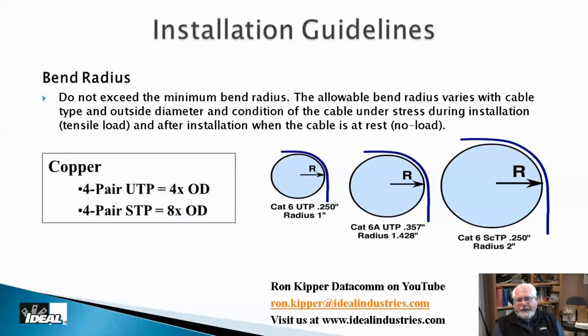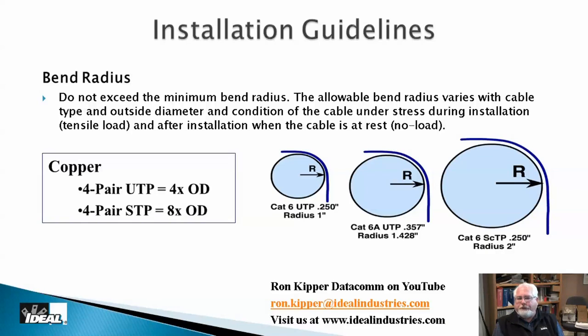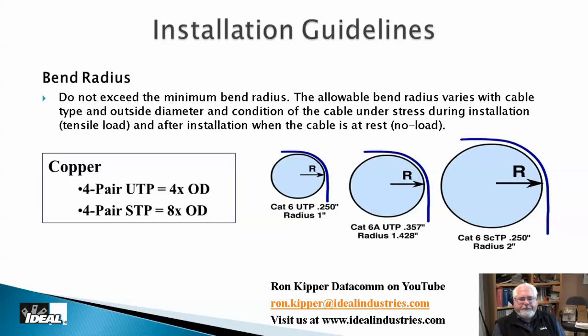Bending radius for UTP cable should be no tighter than four times the cable's outer diameter. Most category cable is roughly a quarter inch in diameter, so the minimum bend radius is one inch — meaning the tightest loop you should form is two inches in diameter. Cat 6a and larger cables require an even larger bend radius. STP cable requires eight times the outer diameter, likely to prevent deforming the internal shield.